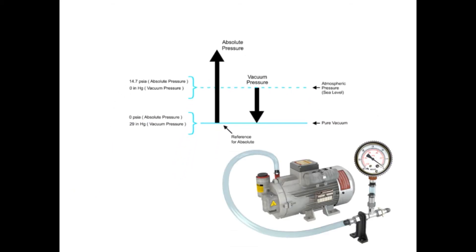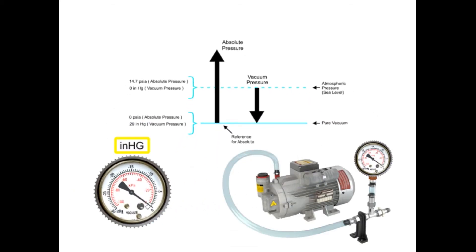The unit of measurement for vacuum is inches of mercury. At sea level, the measurement scale indicates 0 inches of mercury. And at pure vacuum, the measurement scale indicates 29.92 inches of mercury.